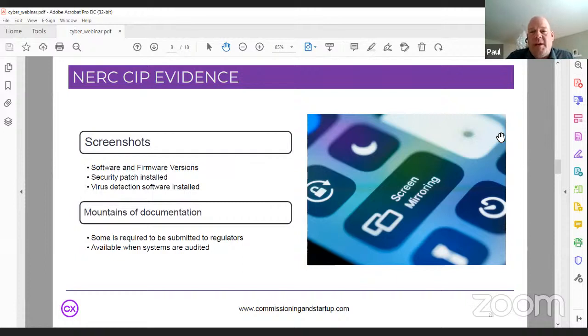This would also include any touchscreen visual HMI display on an HVAC unit, a pump, or a VFD, whatever kind of controller you have. You may take a picture or screenshot to show that the most current version of software and firmware is installed and up to date. Any security patches installed need to be documented with a screenshot, and your virus detection software needs to be shown as up to date and current. This can generate mountains of documentation to demonstrate cyber compliance.